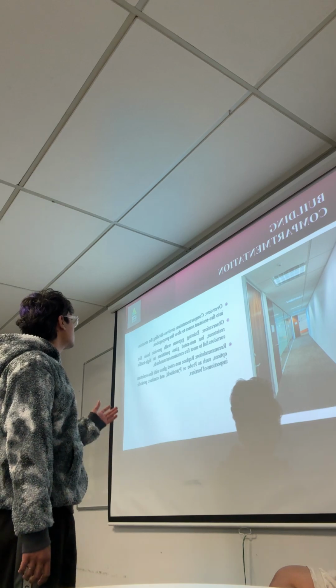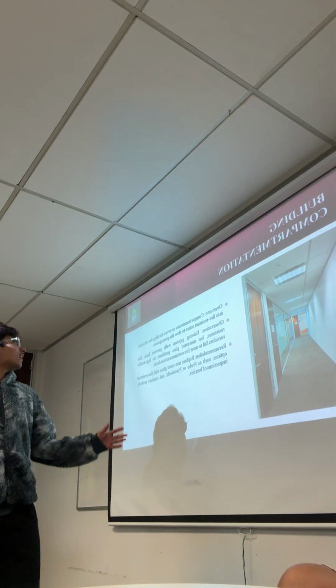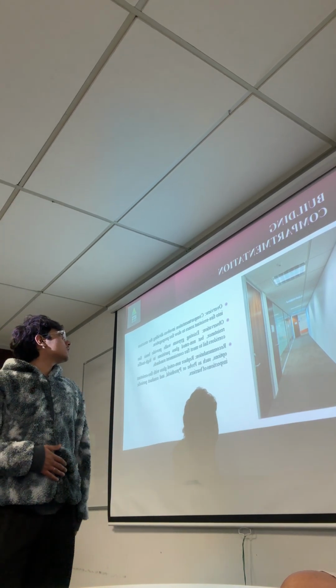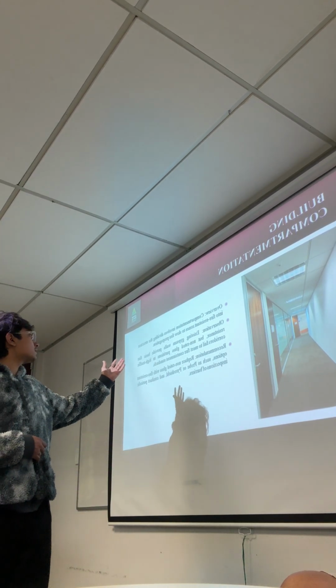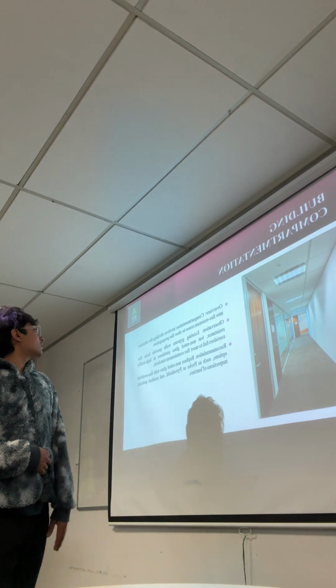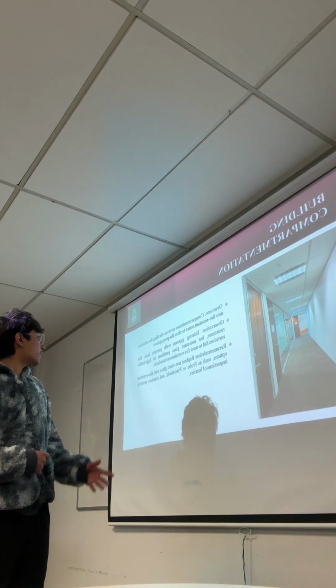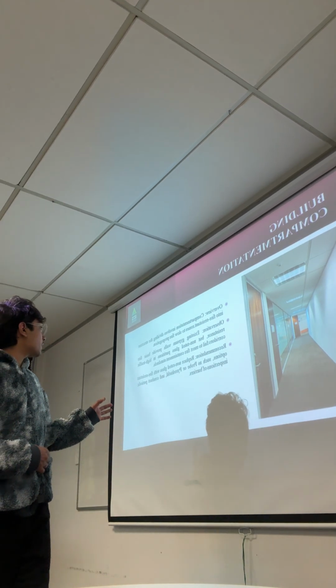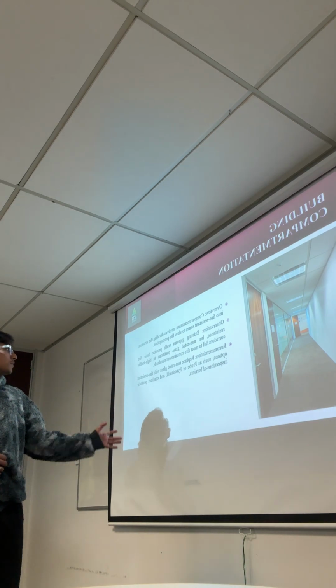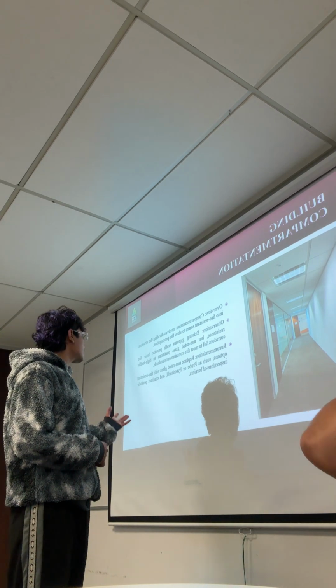So similarly, building compartmentation involves dividing the structure into fire resistant zones to slow the fire propagation. Existing gypsum walls provide basic fire resistance but non-rated glass partitions in high traffic corridors fail to meet fire containment standards. So non-rated glass should be replaced with fire resistance options such as Pyrobel and Pyrosil, and periodic inspections of barriers should be conducted.